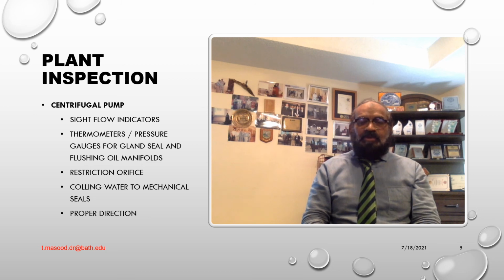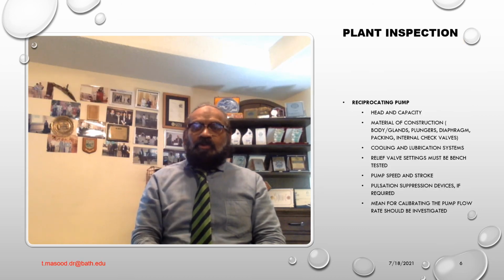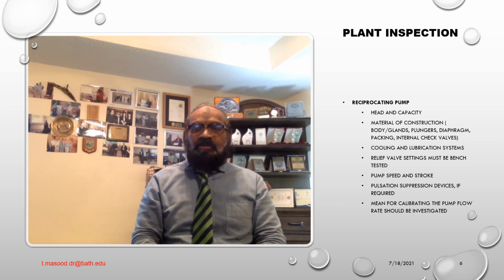Okay, next is reciprocating. Okay, reciprocating pumps. The reciprocating pumps or vendor information should be checked against the specifications to verify agreement on the following points. Number 1, head capacity, minimum or normal and maximum. Material of construction of body, glands, plungers, diaphragm, packing, internal check valves. Next, cooling, lubrication systems, pressure or temperature rating. Relief valve setting must be bench tested. Pump speed and stroke. Pulsation suppression devices if required. Means for calibrating the pump's flow rate should be investigated.